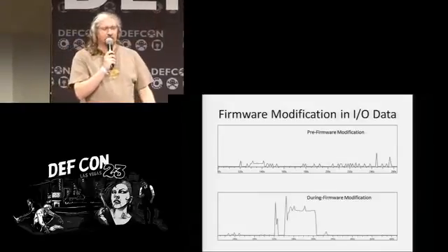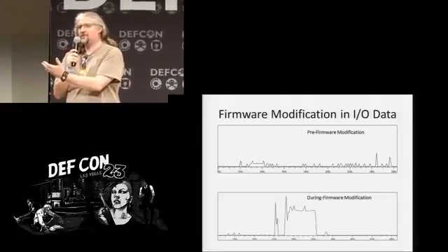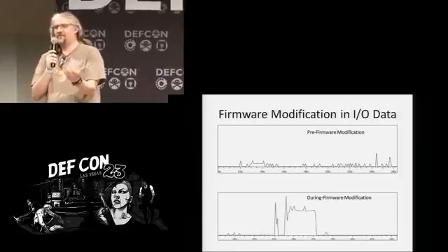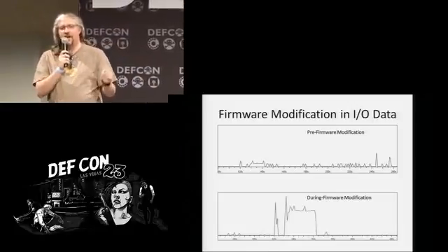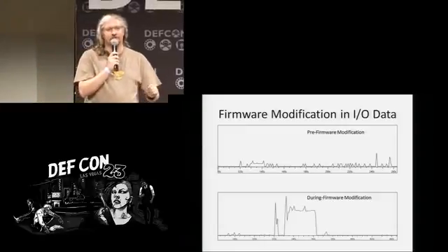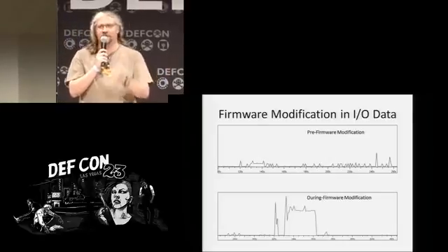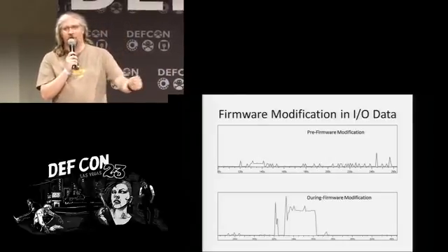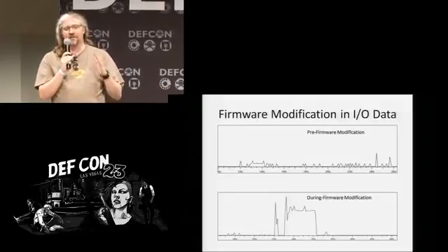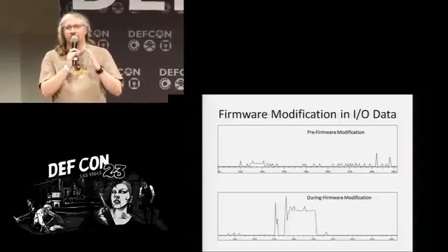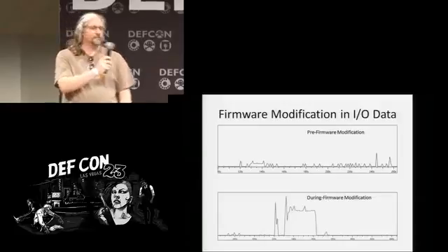Excellent, right? So the point here being, we're talking about doing change control using Wireshark. It doesn't have to be security stuff, but you should know if anyone tried to change the firmware. Not just sign a piece of paper that everyone in the facility agrees to not change the firmware unless they go and speak to Ted or SCADA or whoever it is, but actually check the wire to see if these upgrades are happening at times they shouldn't be. And I think there's something to be said for merging the idea of some security monitoring and your change control processes that already exist in the plants.